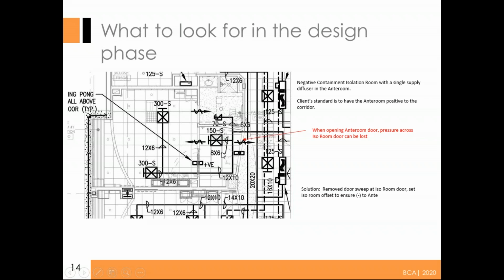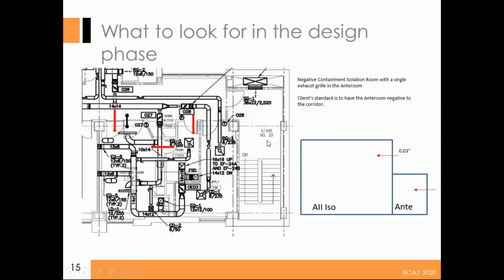And if you do an egress test where you open up the ante room to corridor door, then the pressure here gets lost and these negative isolation rooms can lose containment. This is a common thing that we see, and sometimes we'll follow a balancer after they balance these rooms. And then when we do an egress test, we find that the negative rooms lose their pressure. This can also happen for negative rooms. I'm going to skip past that, but basically it's the same thing for negative rooms.